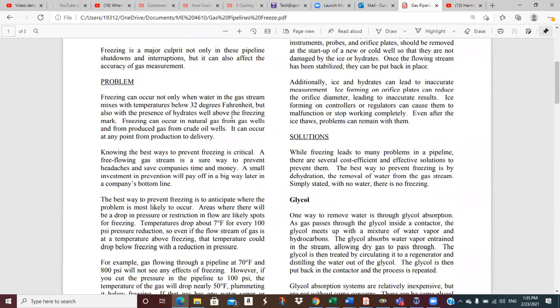The problem: freezing can occur not only when water in the natural gas stream mixes with temperatures below 32. There's going to be water vapor inside the pipe, because this stuff's coming out of a well, and you're not going to get all the water out of it. But also with the presence of hydrates, well above the freezing mark. Freezing can occur in natural gas from gas wells and from produced gas from crude oil wells. It can occur at any point from production to delivery. So knowing the best way to prevent this is obviously pretty important, especially in Texas right now.